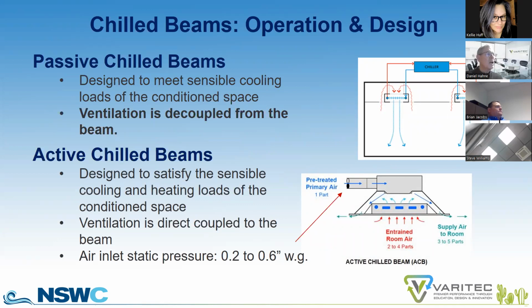Again, there are two types of chill beam approaches. One is the passive chill beam approach. It's essentially a sensible cooling device only. You wouldn't want to heat in this application, though there may be unique applications for using it in the heating mode in a mixed air environment as supplemental heating. The ventilation side is completely decoupled from the chill beam. The rocket science behind this technology is a chill water coil is located in the ceiling, and we allow for the natural forces of convection to occur in a thermally stratified environment.